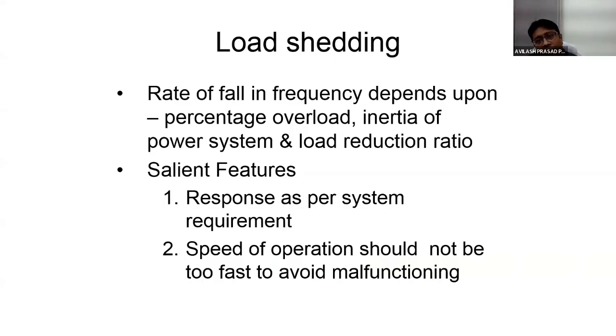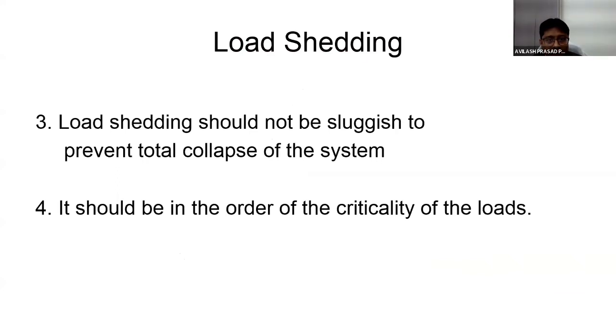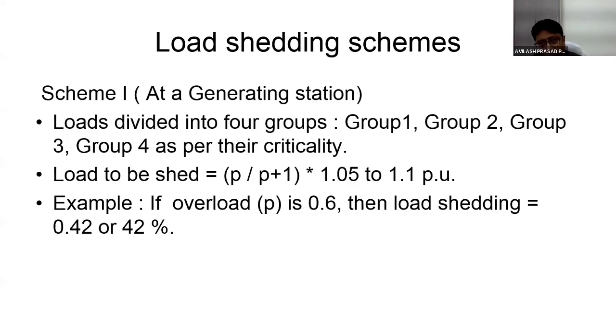The load shedding rate of fall of frequency depends upon the percentage overload, inertia of the power system, and load reduction ratio. Salient features are response as per system requirement, and speed of operation should not be too fast, to avoid malfunctioning. Load shedding should not be sluggish, to prevent the total collapse of the system. It should be in order of the criticality of the loads. So we have our scheme 1 at the generating station, that is, the load is divided into 4 groups, group 1, 2, 3 and 4, as per criticality. And the formula for the load to be shed is P upon P plus 1 into 1.05 to 1.1 PU. For example, if overload is 0.6, then the load shedding is 0.42 or 42%.